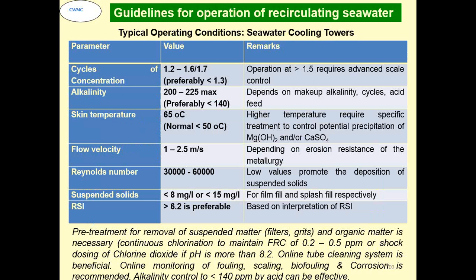See, this is the tentative guideline that we had developed for operating with a seawater system. Cycle of concentration 1.2 to 1.6, maximum 1.7, preferably less than 1.3 if we are not dosing anything. If you are going beyond that, that means we have to do the chemical treatment of the seawater also. Alkalinity should be about maximum 225. Skin temperature not more than 65 degrees. Below 50 degrees is normally the acceptable range.